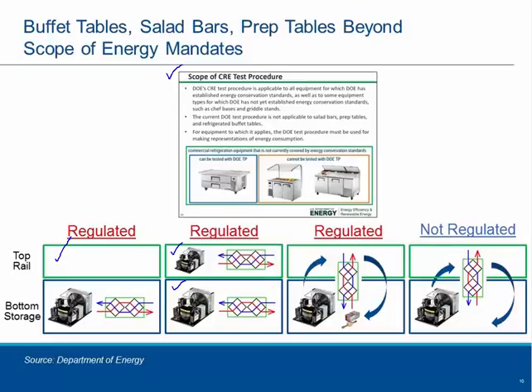That is regulated. Then you have systems where you have one condensing unit that is sharing the heat exchange and is cycling between the top rail and the bottom storage. And the key criteria here is the effect of the solenoid valve. The solenoid valve is what allows the distribution of heat exchange between the top rail and bottom storage, depending upon a control circuit that will measure what the runtime would be on the top rail and the bottom storage. If that is the case, there's a test procedure for that. That will be regulated. It's for these systems where you have a condensing unit sharing on the top and the bottom, but no solenoid valve.